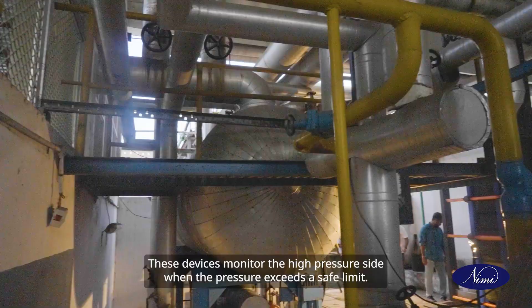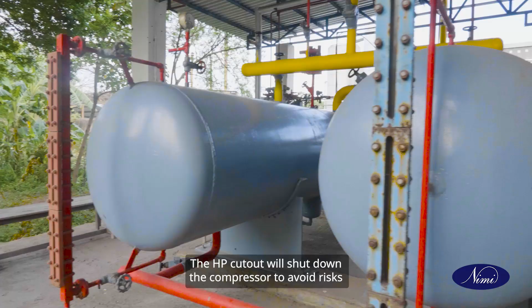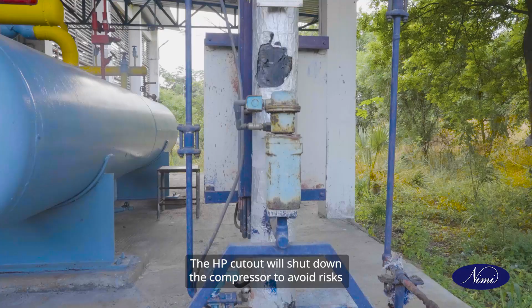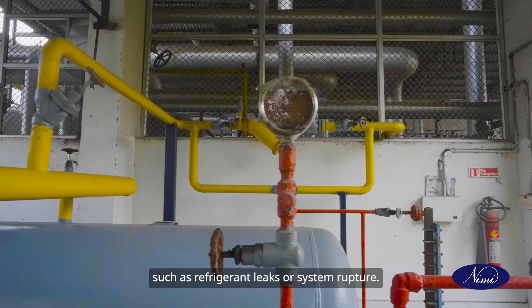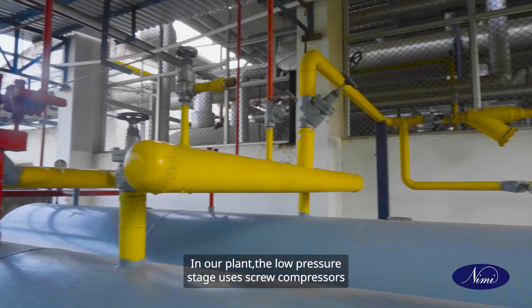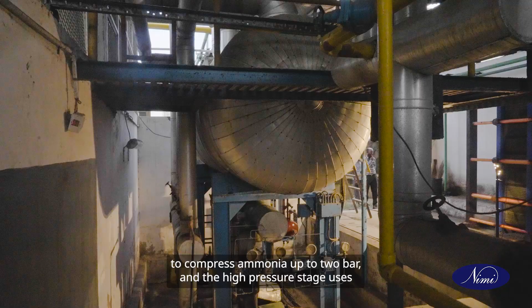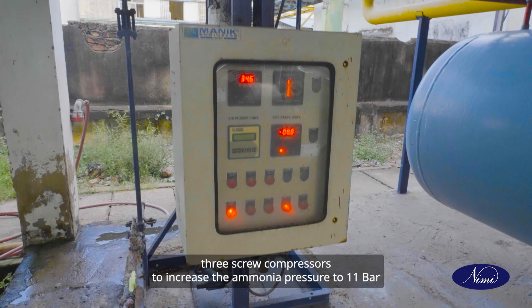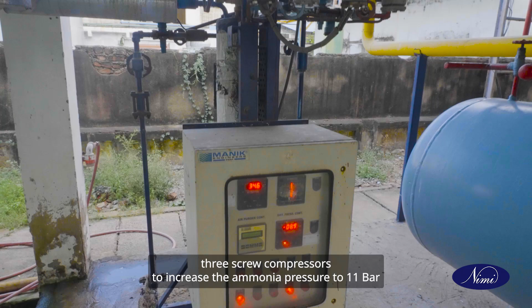HP cutouts. These devices monitor the high pressure side. When the pressure exceeds a safe limit, the HP cutout will shut down the compressor to avoid risks such as refrigerant leaks or system rupture. In our plant, the low pressure stage uses screw compressors to compress ammonia up to 2 bar, and the high pressure stage uses 3 screw compressors to increase the ammonia pressure to 11 bar.